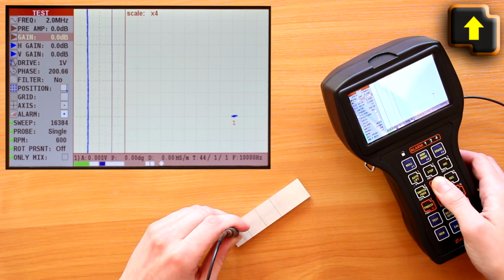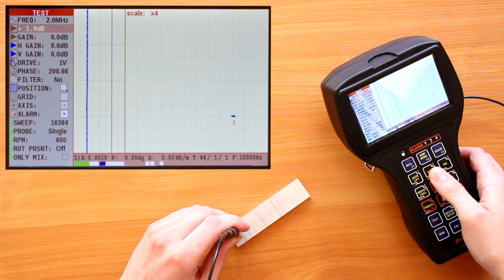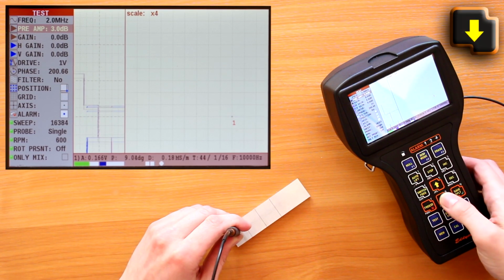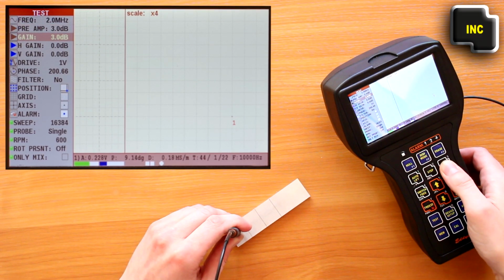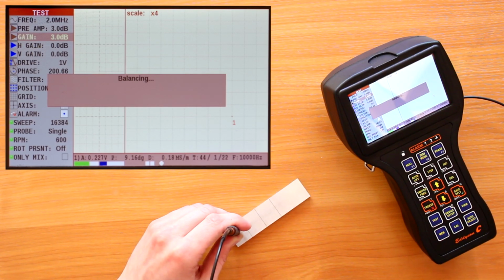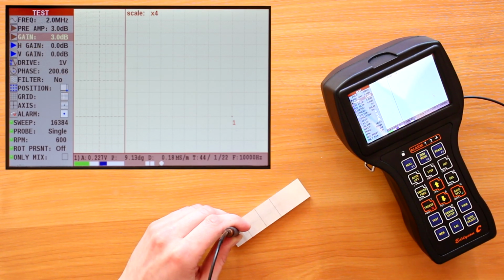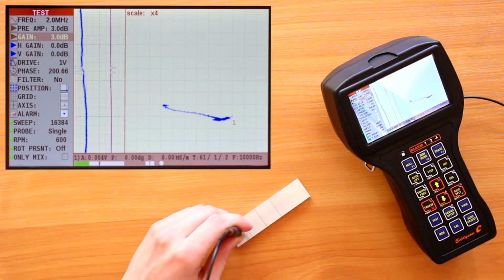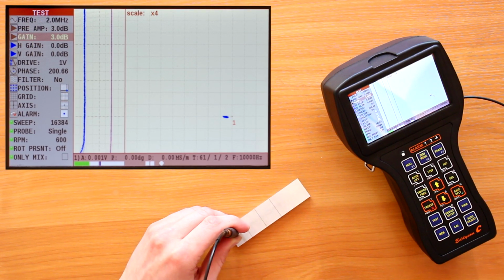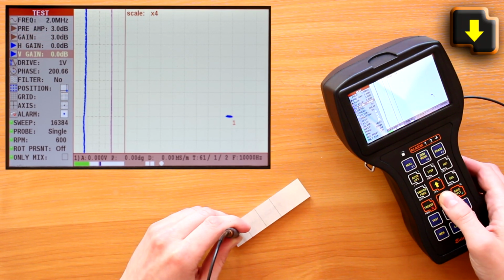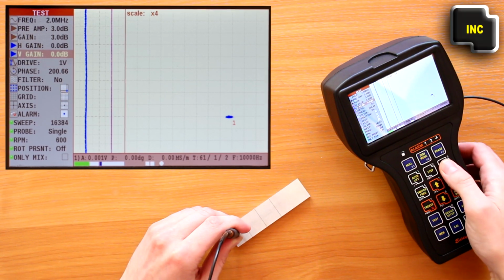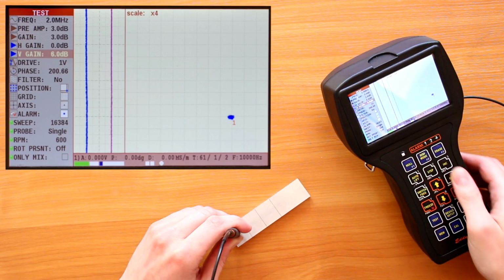Increasing the gain on preamplifier and amplifier, you should maximize the signal amplitude if necessary. After changing any parameter that affects the absolute value of the signal, it is necessary to perform balancing by pressing F1. While testing aluminum alloys, it is recommended to use the vertical gain for the visual spread of signals from the distortion and signals from a defect.